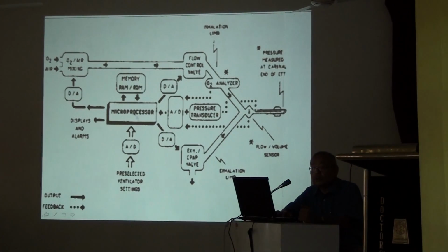All of this you can put to this microprocessor, and the microprocessor has got a book inside in its memory, that is read only memory. Random access memory is put here. Random access memory picks up the signals from these two, the oxygen analyzer and flow sensor, and interacts with the ROM, which is already inside the brain of the computer. They interact and finally they dictate the terms to this mixer, flow control valves and exhalation valve. There are a lot of other things, but I don't want to confuse you because this is the first class for you. So I don't want to confuse all these things. How a machine works, basically you can learn.